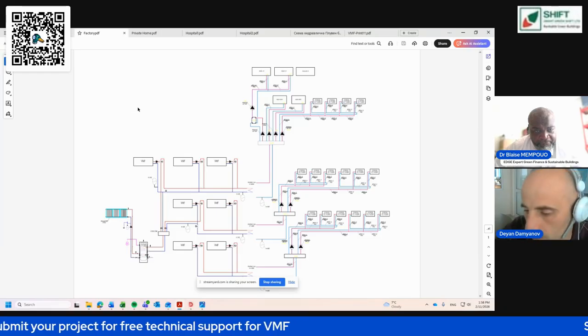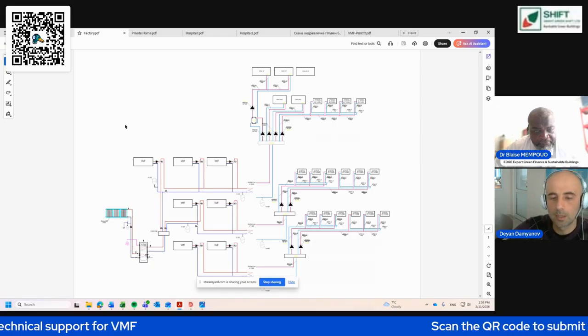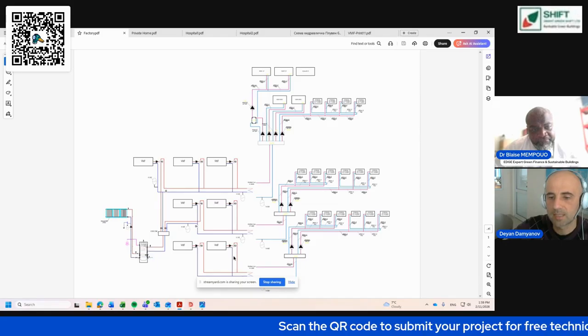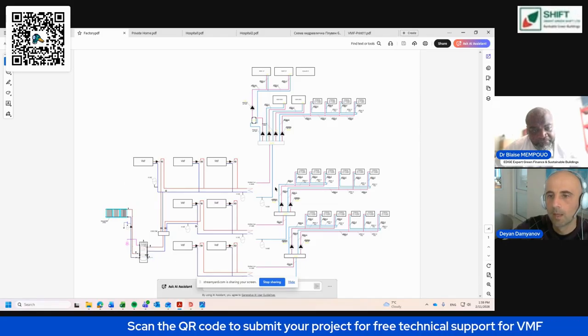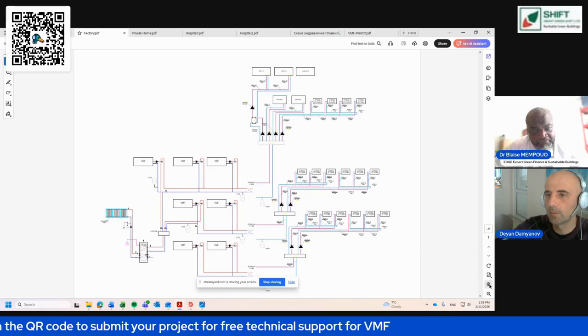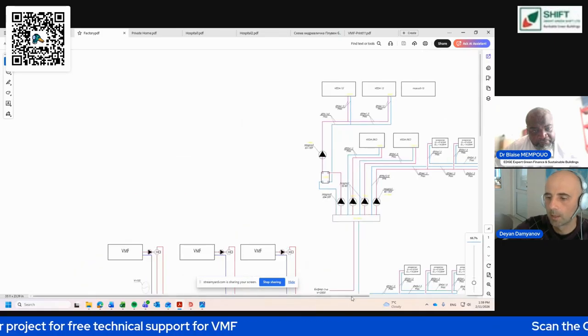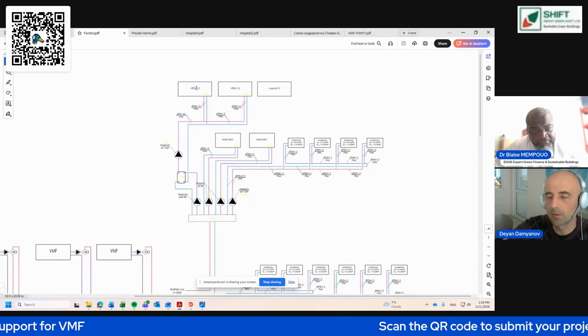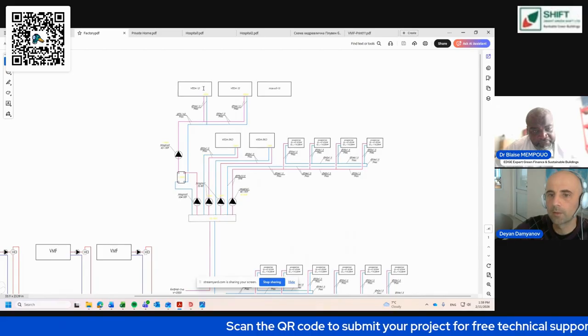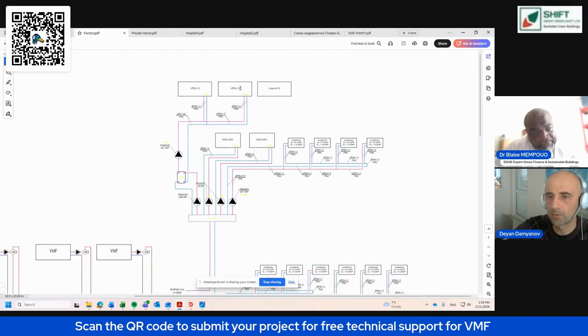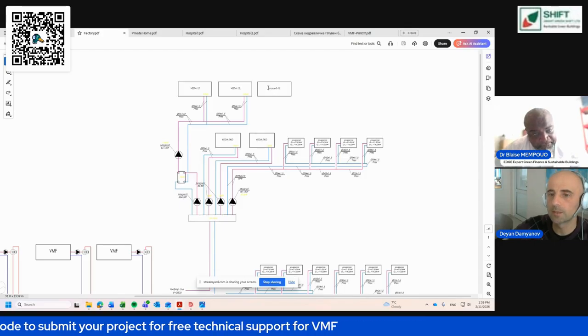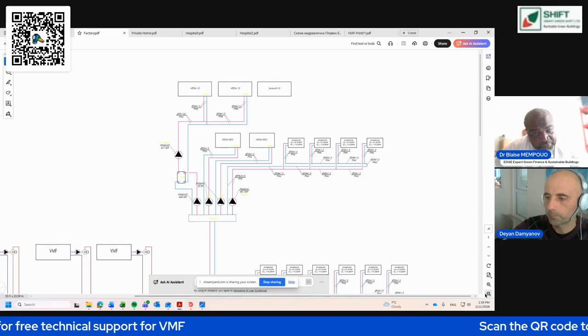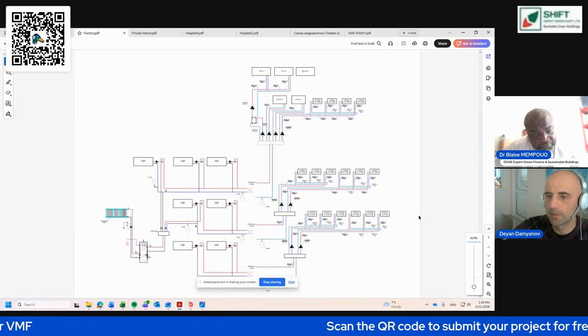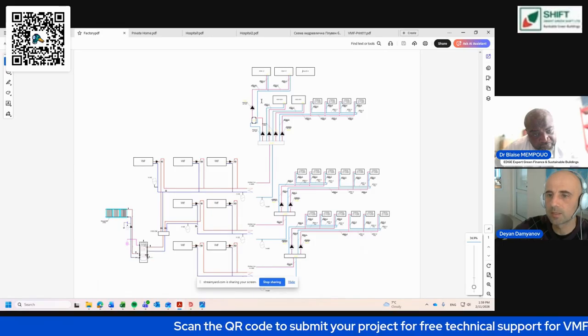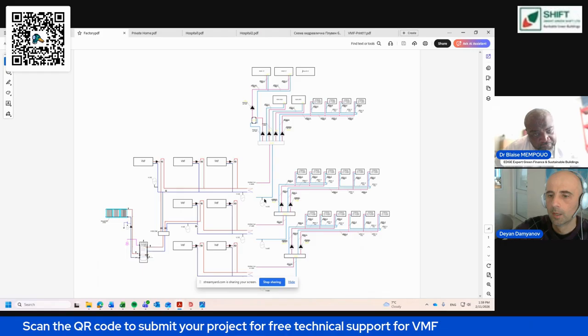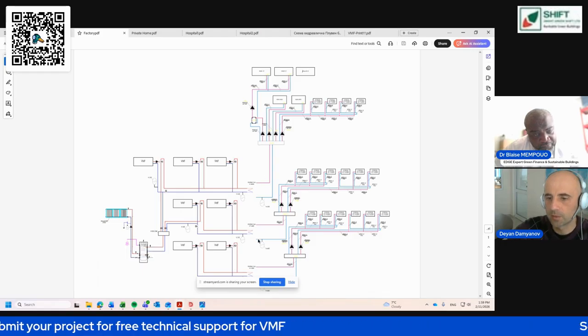The size of this project is quite large. As you can see, we have 7 VMF units in total, plus 3 large ventilation units serving different parts of the production: one for 13,000 cubic meters per hour, another 13,000 cubic meters per hour, and another 15,000 cubic meters per hour. Part of those ventilation units are supplied with hot or cold water through the buffer tanks of each subsystem.